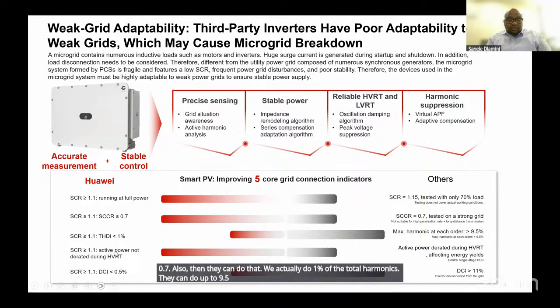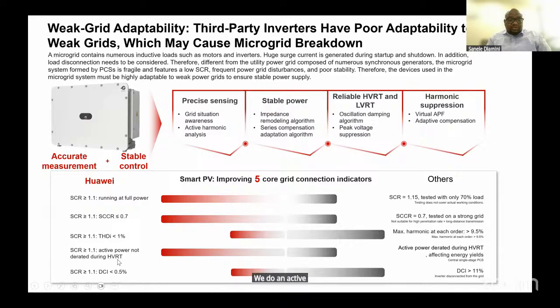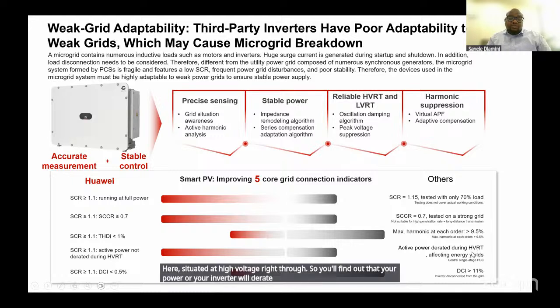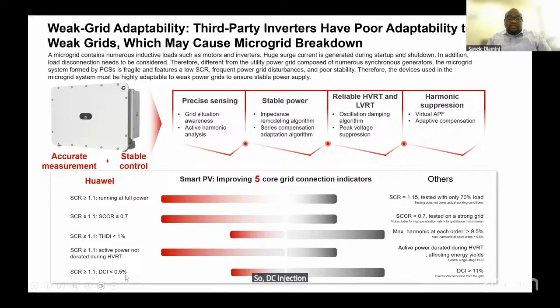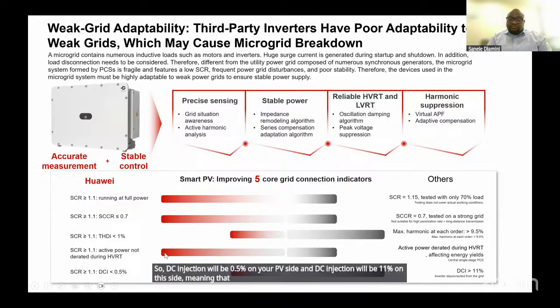We do active power not derated during high voltage ride through. Here it's derated at high voltage ride through. So you'll find out that your inverter will derate when there's a high voltage ride through on this side. DC injection will be 0.5% on your PV side, and DC injection will be 11% on this side, meaning that we are also better on this.